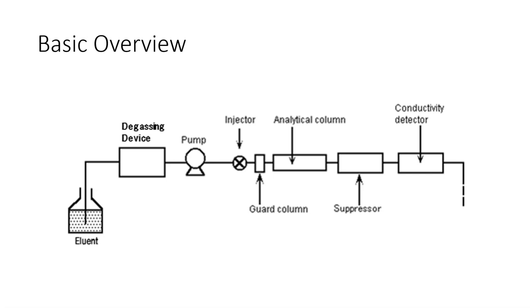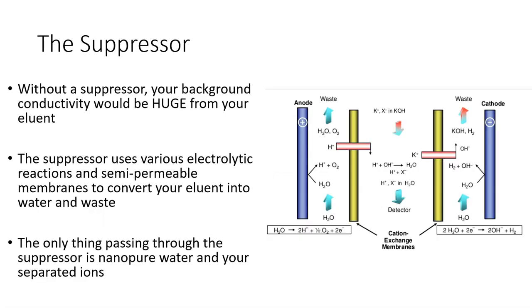But there's one more very important component before we get there. This is the suppressor. So without a suppressor, your background conductivity would be huge from your eluent. We're using acid and base concentrations in our eluent and that has a lot of conductivity, so we need to suppress that first. The suppressor uses various electrolytic reactions and semi-permeable membranes to convert your eluent into water and waste.